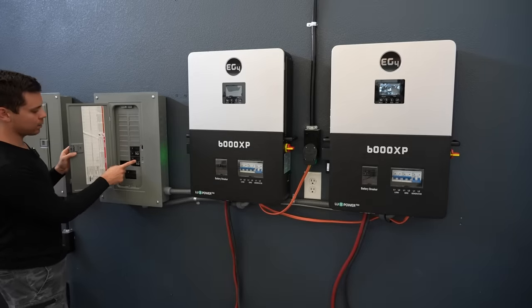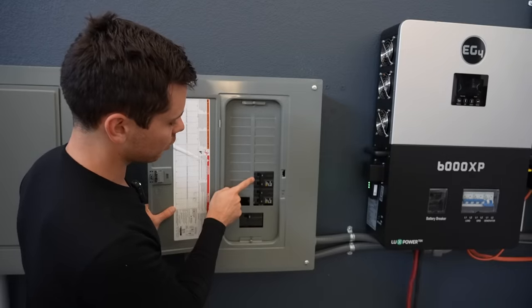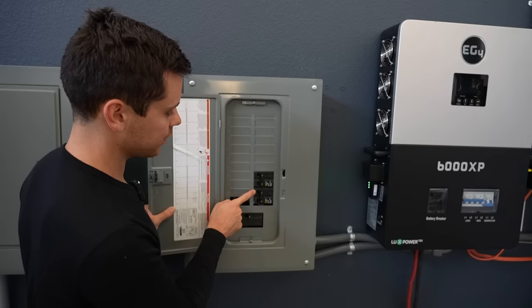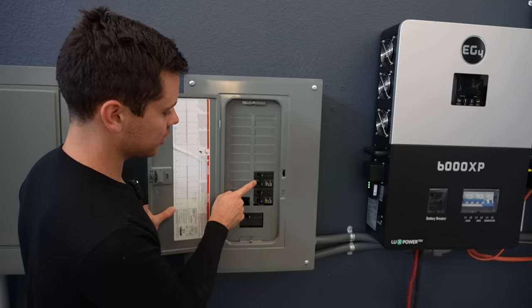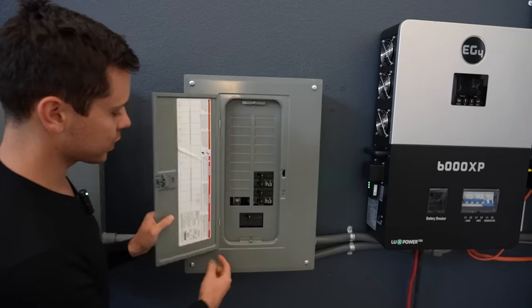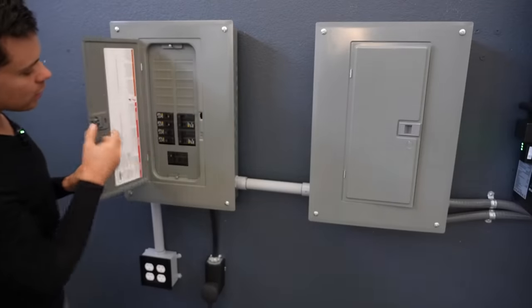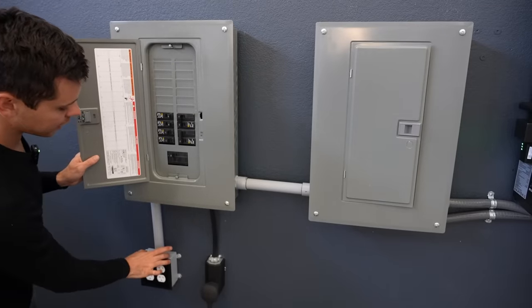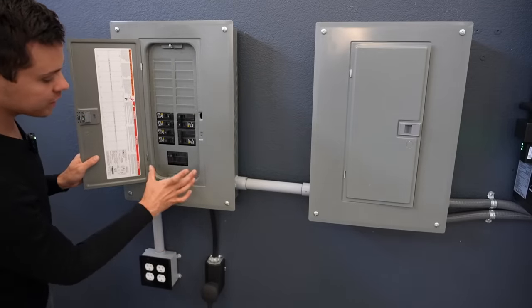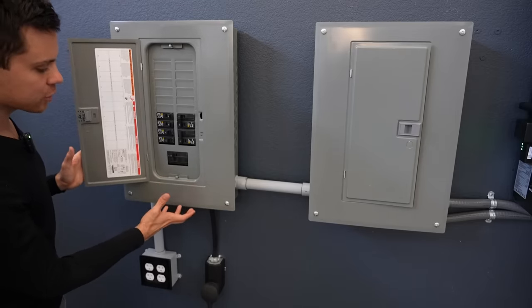Then you use this as the combiner box and for each unit we have a 40 amp breaker. This is inverter number one and inverter number two. This is hot one and hot one supplying one bus bar and then hot two and hot two supplying the other bus bar. And then we have a disconnect. This runs over to the other panel and this is our load center.